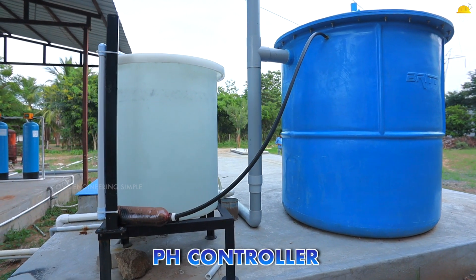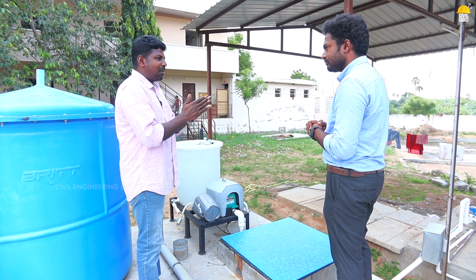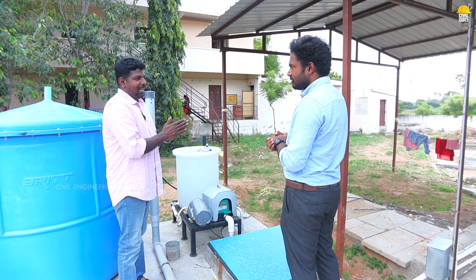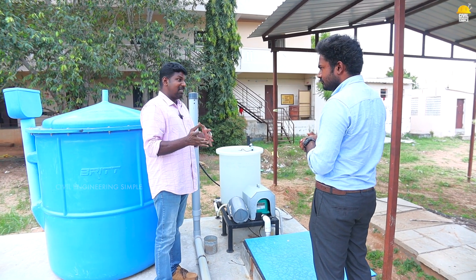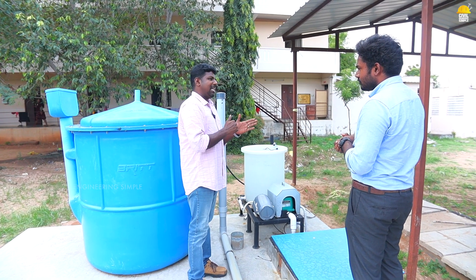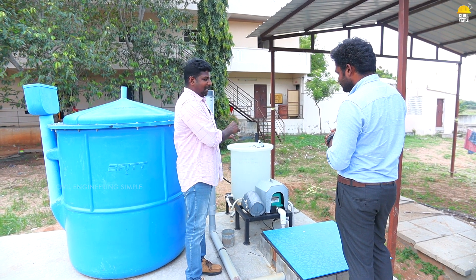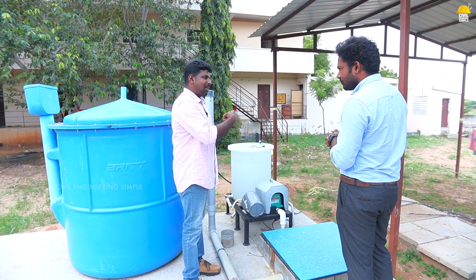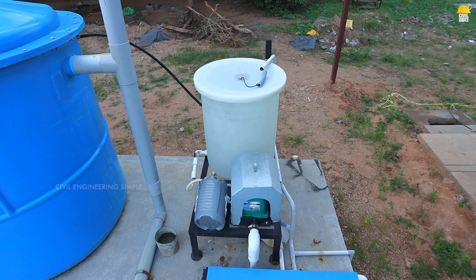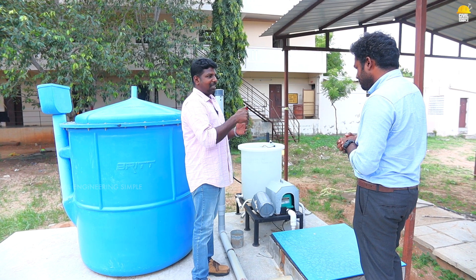This is the first tank with a pH controller. There are various components in the water and the pH will vary. The pH should be maintained between 6.5 to 8 for regular treatment. The kitchen water can bring pH down to 5.5, so this water will be balanced. The kitchen and other water will be balanced to a good pH level.